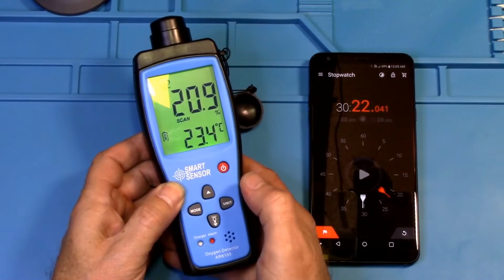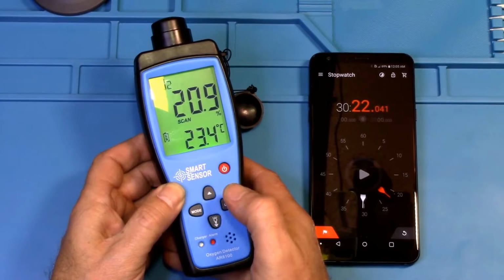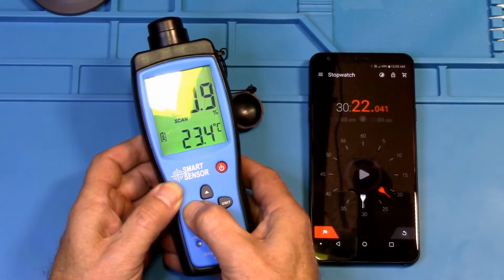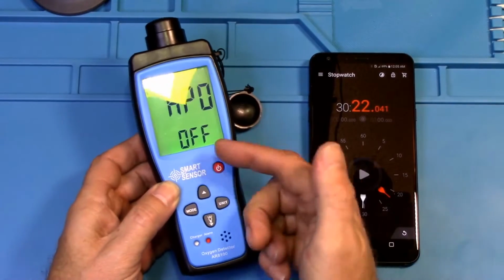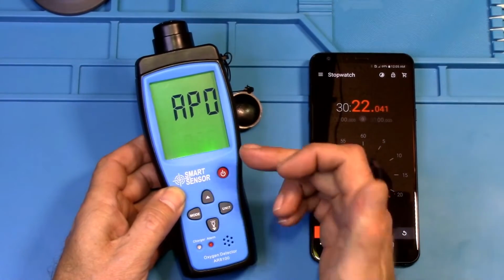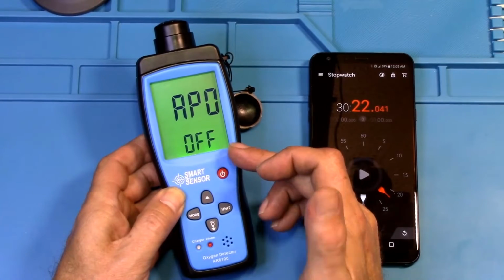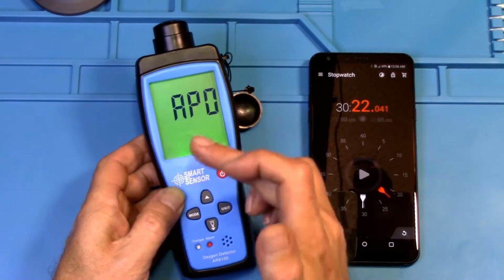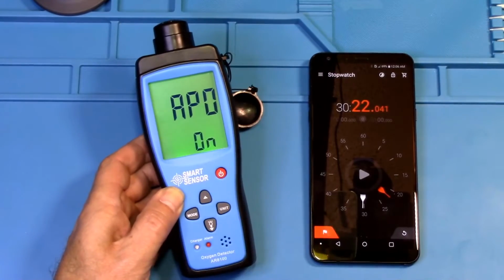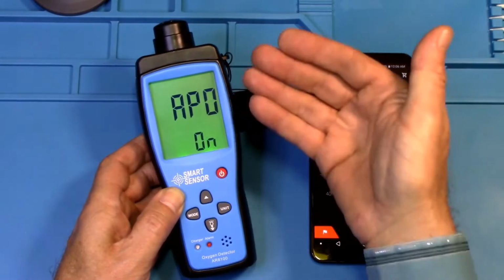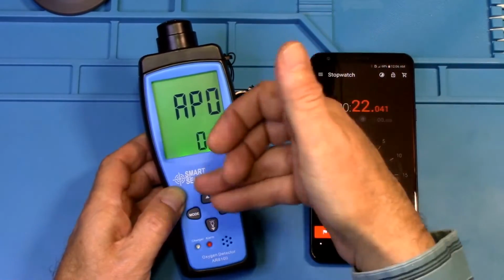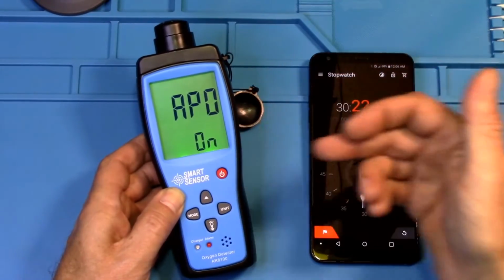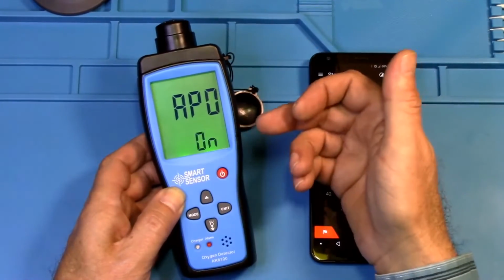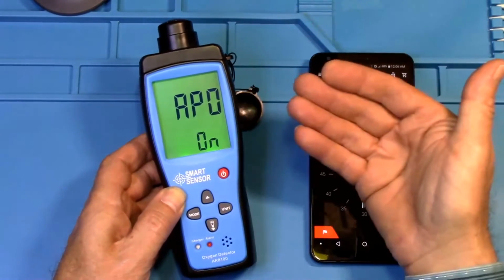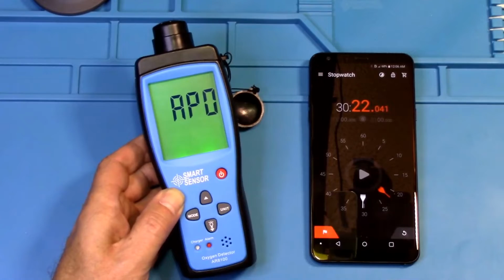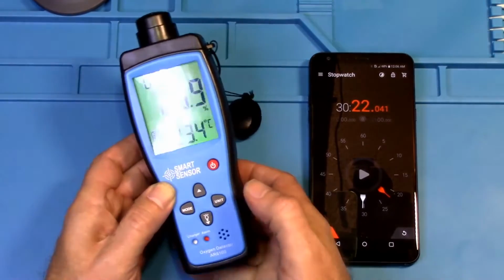Just make sure that if you want to disable the automatic power off, press and hold the mode button for a couple seconds or so. Okay, and it's showing off. Make sure that before you start this calibration process you turn the device on and make sure the APO is off, because if it's on, then you won't be able to complete the calibration. Once you power this off, it remembers the setting, and once you power it back on, whenever you try to do the calibration steps, this is going to power off automatically after 10 minutes. So you won't be able to let it sit for 30 minutes. So make sure that this says off before you turn it off to start the calibration process.